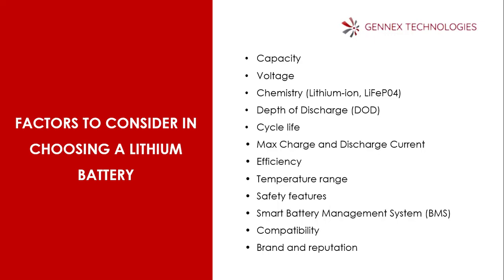Maximum charge and discharge current. This is very important. They come in different sizes, different capacities. So you look at it. Lithium ion has high discharge and charge current. So you look at it. Does it match what you want to do? Mind you, the batteries are sensitive to surge. They can shut down. They have been protected. So if the surge from the load that you want to put on it is higher than the surge handling capacity of the lithium ion, it's going to shut down. It's not going to get damaged. So you should be careful that the surge from your load doesn't get to the maximum surge capacity of the battery, so that you don't experience a shutdown when your load wants to start.